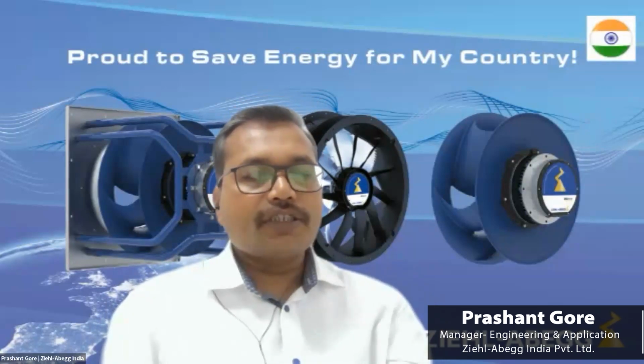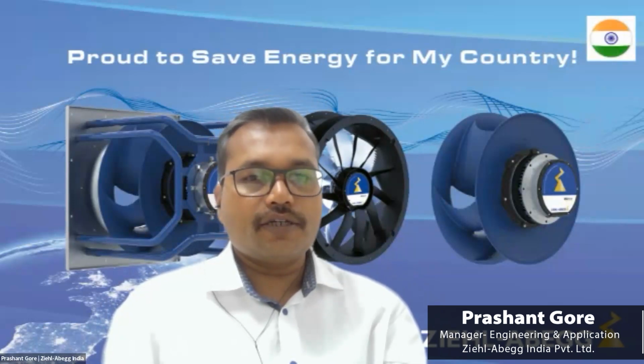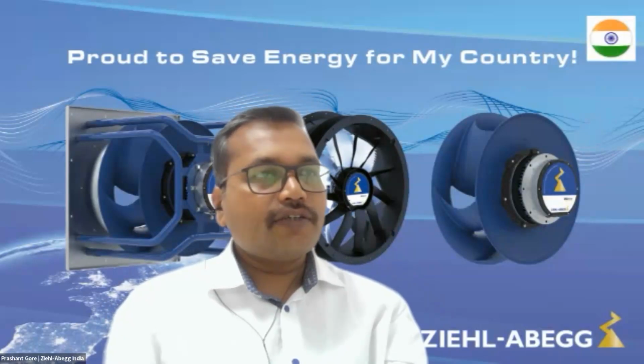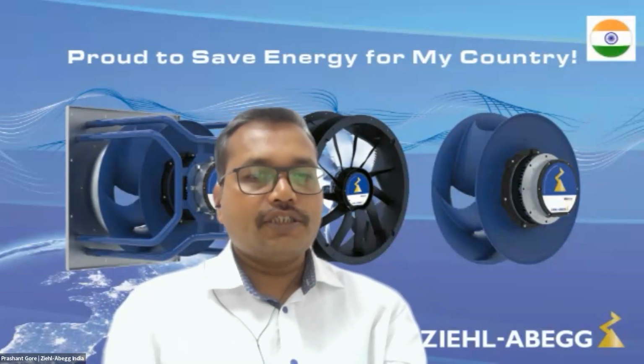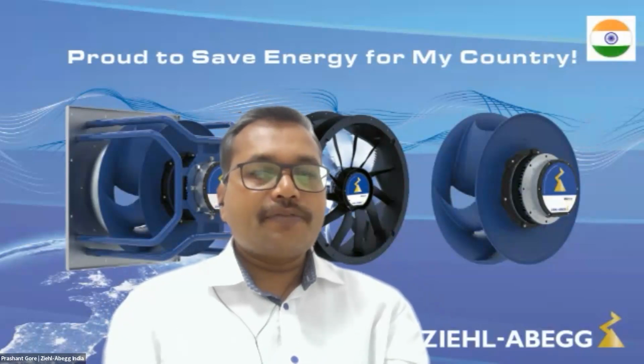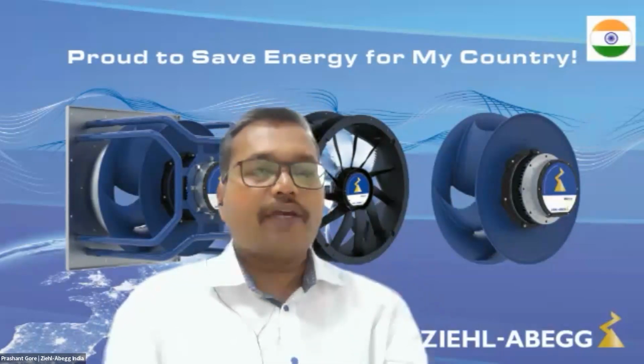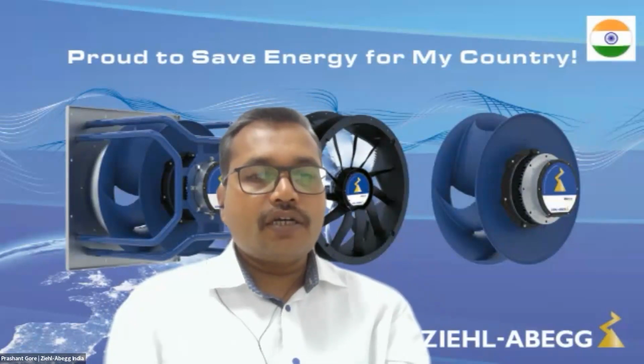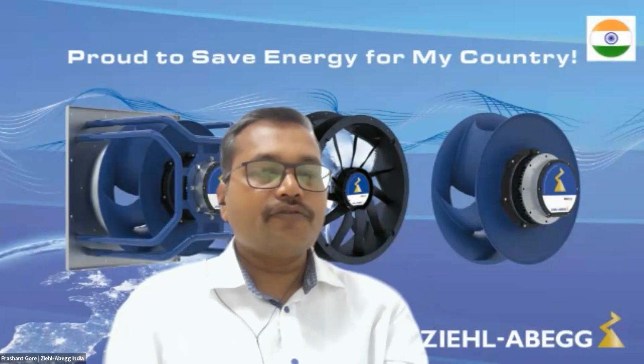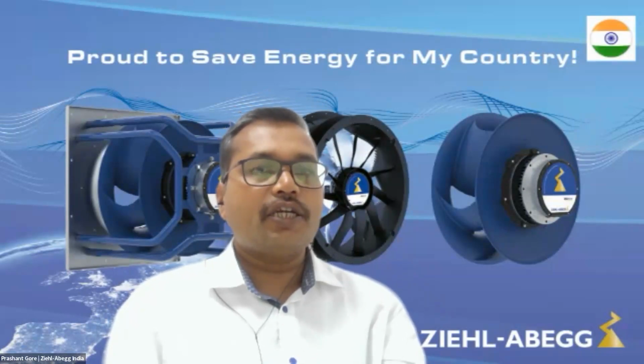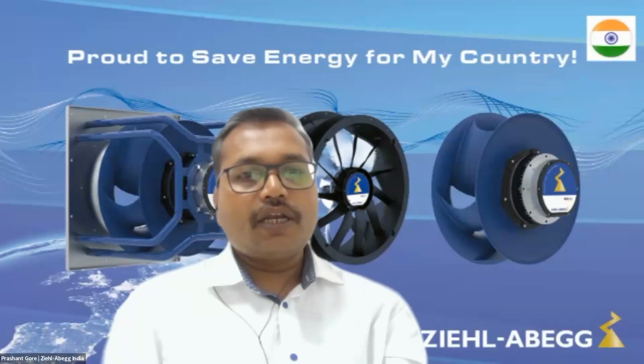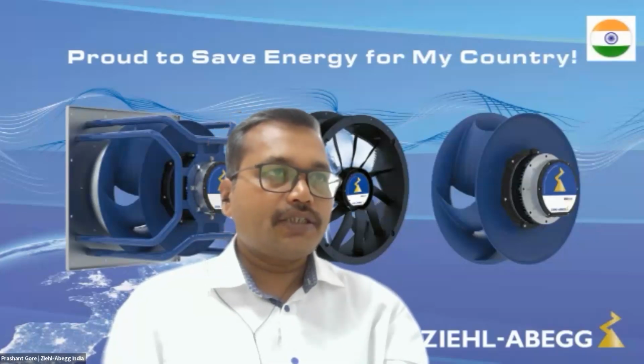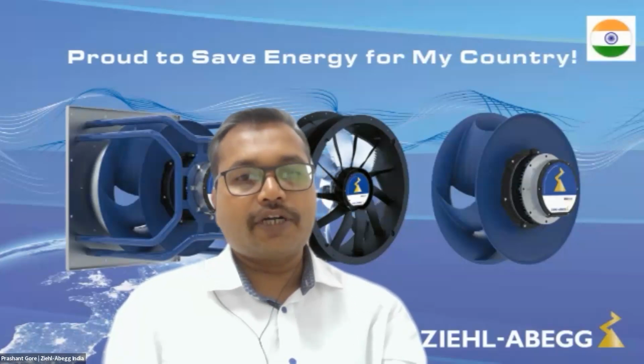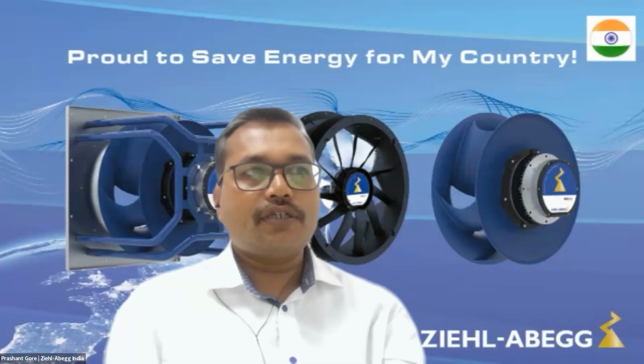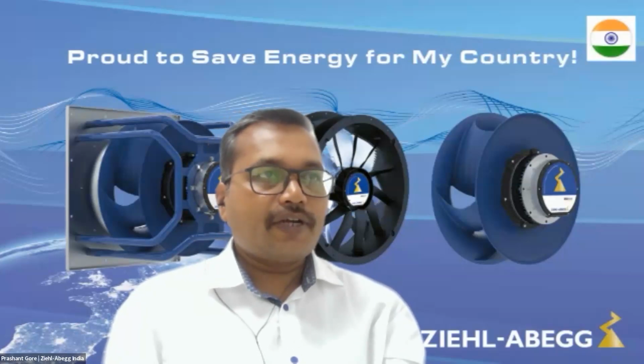Good question indeed. The placement and operation matter, and operation is most important based on the load requirement, since load in a data center is not constant but varies. You can integrate fans so that airflow changes as per requirement, aligning with best practices like cold or hot aisle designs and variable speed fans. Fan placement is also important to reduce turbulence and ensure efficient airflow through the heat exchanger. This improves thermal management, and it depends on the OEM - we're already in contact with different OEMs to get recommendations from fan manufacturers.